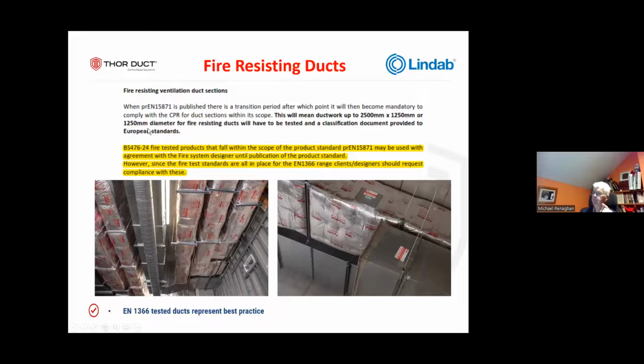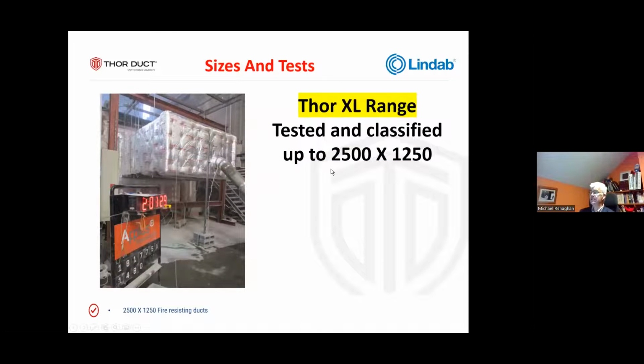For fire resisting ducts, because the standard 15871 has not been officially published in the sense that it is a harmonized standard in CE marking, they are saying that you can use BS 476 by approval of the fire engineer. However, what they do say is that because the EN 1366 testing and classification standards are in place, and the extended field is there up to 2.5 meters for 1250, that EN 1366 should be used. Now, you know and I know, as soon as somebody says you should use that, even though it's not law, that becomes best practice. And in fairness to the Irish industry, they are all trying to use that. Very rarely will they use BS 476. And again, we have tested up to 2.5 meters for 1250, which is a ginormous duct for air.